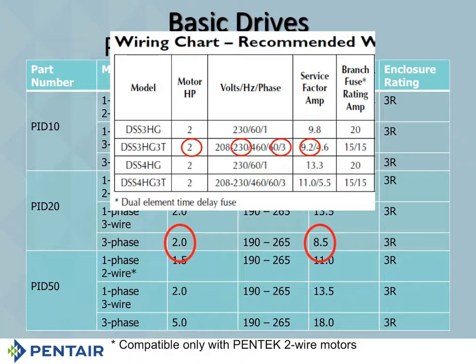We've had a few people try it, and we know it's not going to work. So we're just telling you to be very, very careful. Size the drive towards the max load amps. This pump that we're looking at here, the DSS3 and the DSS4, has a 1.5 service factor. So, of course, you multiply 1.5 times 2, you're going to get 3. And so that's really a 3 horsepower pump. We're just calling it 2 horsepower. And yes, it can mess up a drive. And yes, we have had people try to put a 2 horsepower drive on this 2 horsepower pump. And no, it doesn't work.